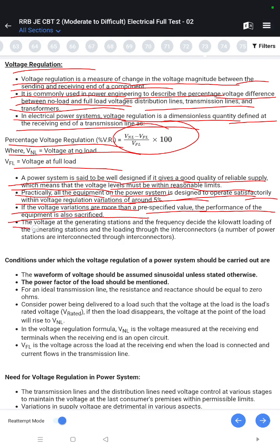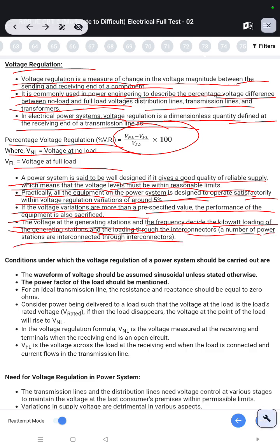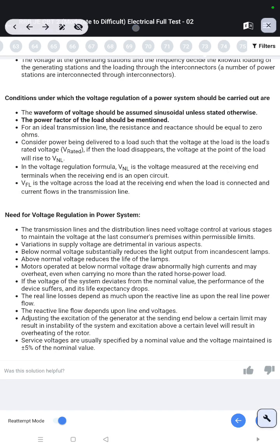The voltage at the generating station and the frequency decide the kilowatt loading of generating stations and the loading through the interconnectors. A number of power stations are interconnected through interconnectors. Conditions under which the voltage regulation of a power system should be carried out are: the waveform of voltage should be assumed sinusoidal unless stated otherwise. The power factor of the load should be mentioned. For an ideal transmission line, the resistance and reactance should be equal to 0 ohms.